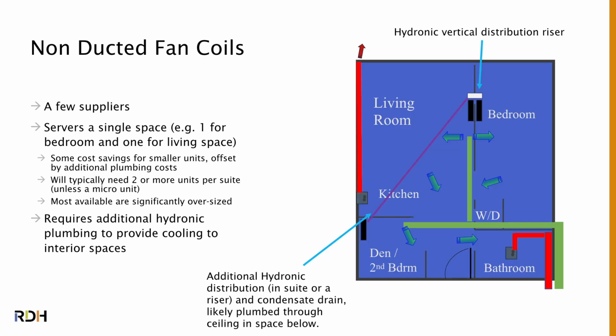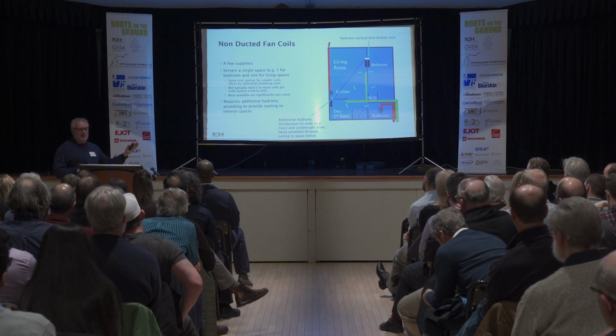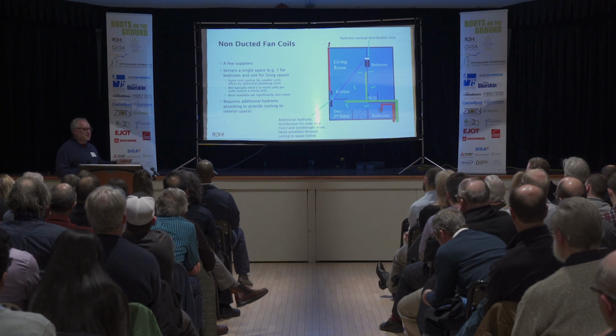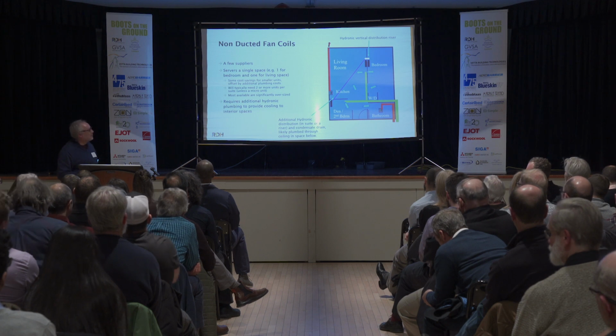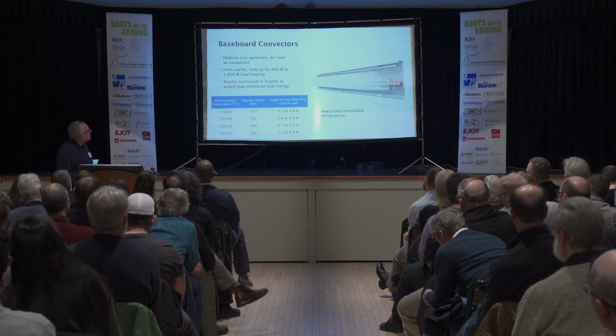You could install them like this, but then the problem is, if I have an interior space, I have to then plumb water over there. You're probably going to do that plumbing in the suite below through their drop ceiling, and also, if you're going to do cooling, you're going to need a condensate drain. So this becomes a little challenge, and this is why a lot of people end up doing air for heating and cooling just in the suite to avoid all this extra plumbing and condensate. Cooling climates have extra challenges.